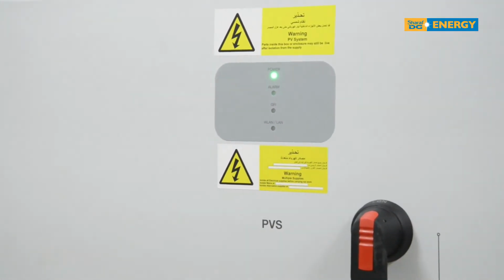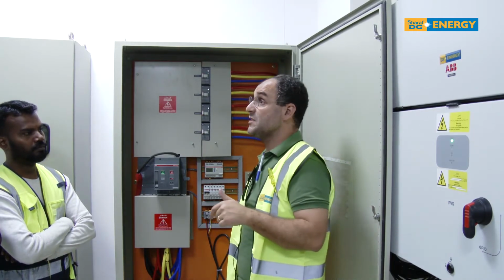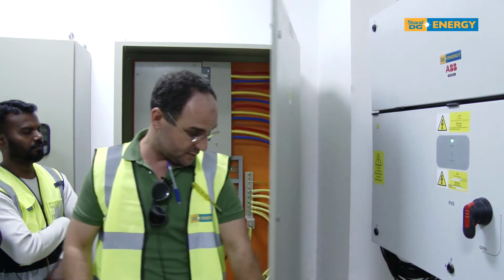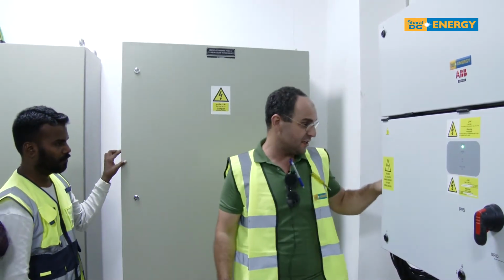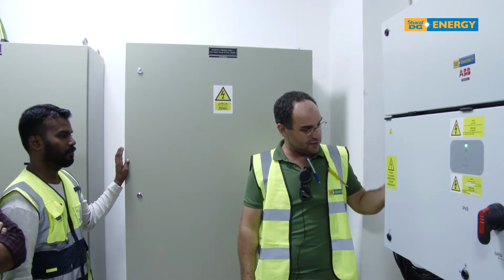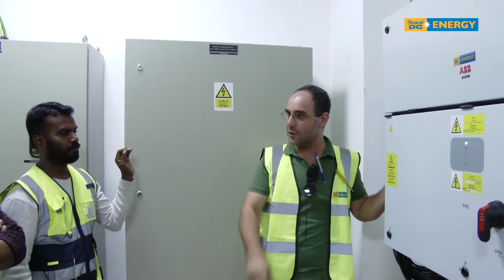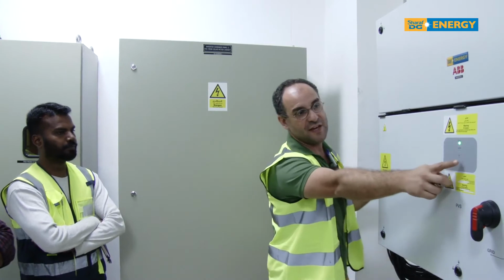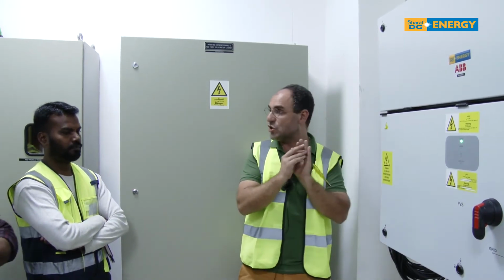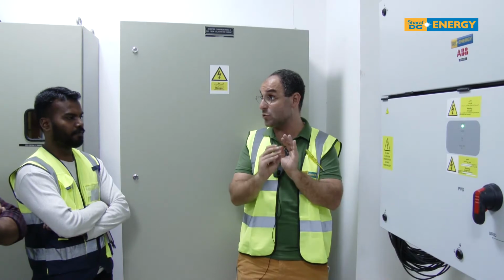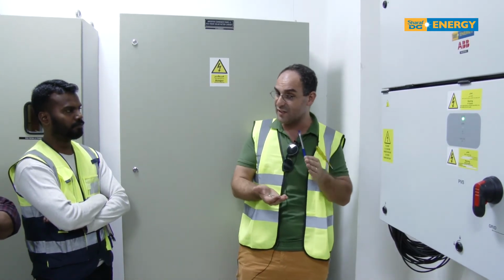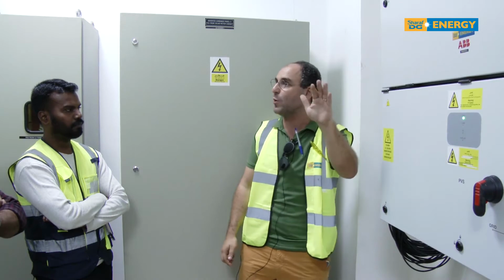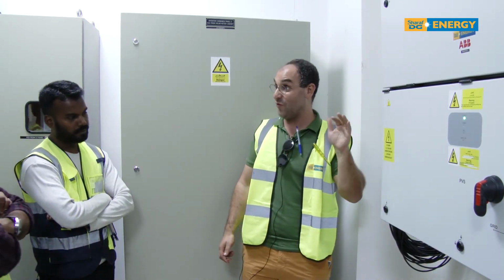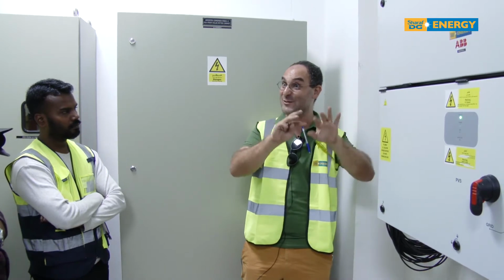And usually when this light is up, it means that on the DC side or AC side, you are having an electrical fault. What does that mean? It means that the circuit, for example string 10, the string that comes in from a particular location on the roof, if it's showing GFI, the inverter will stop by default. By safety procedure it will stop, because GFI means there is current that is not flowing on the cable, it's flowing somewhere else. So by default, it will open the circuit so the current also stops.